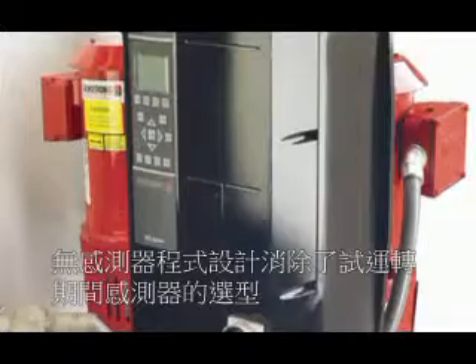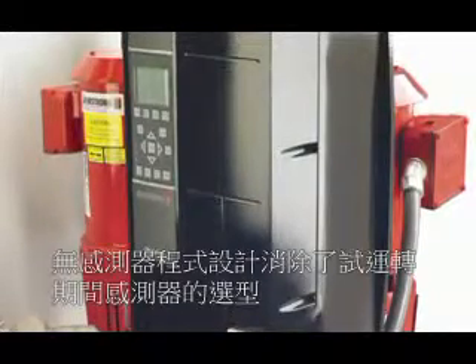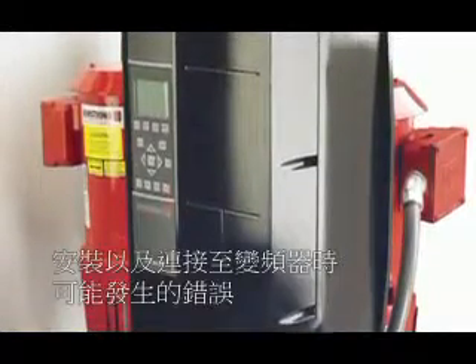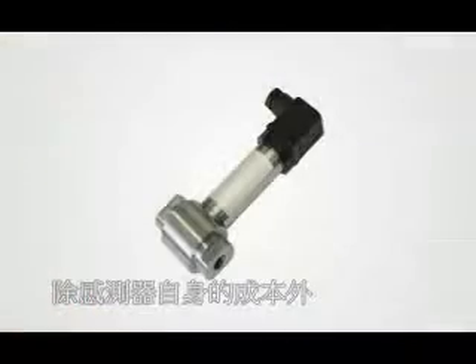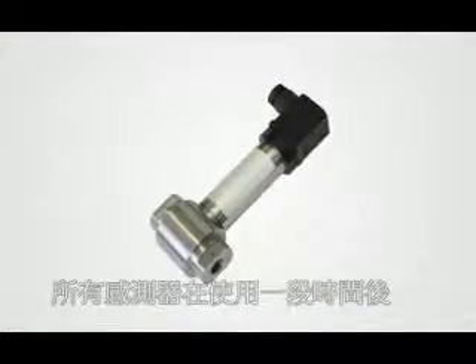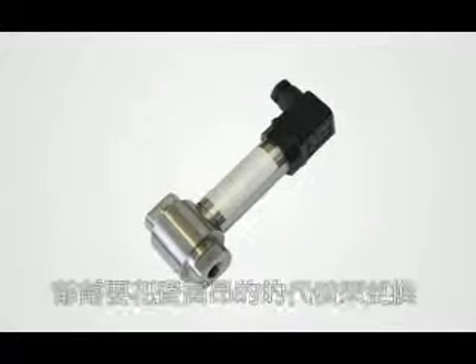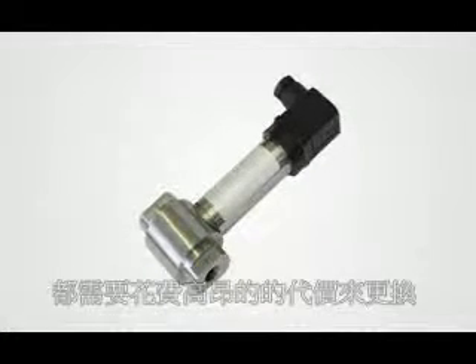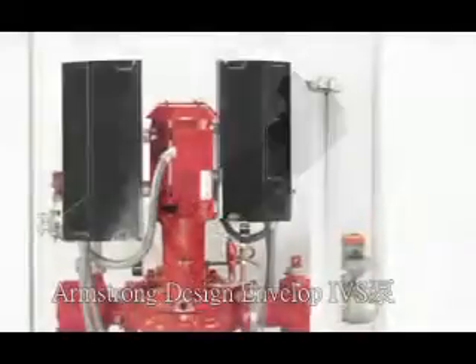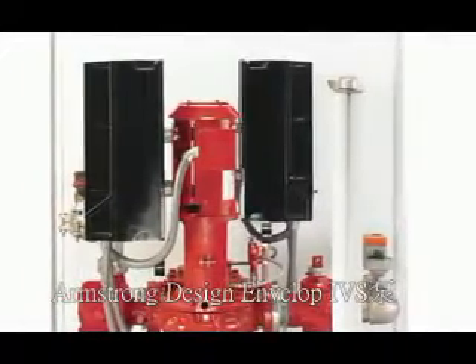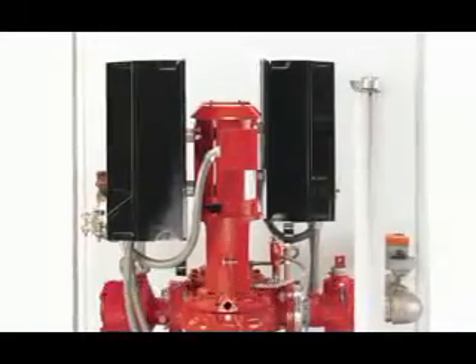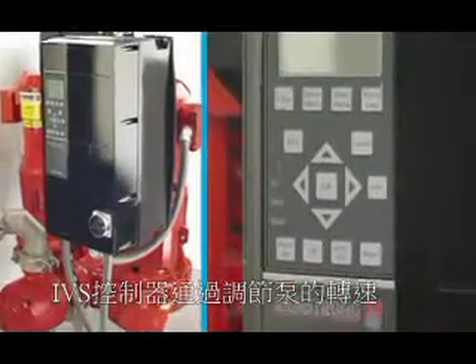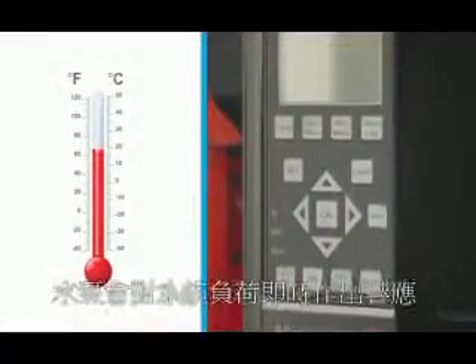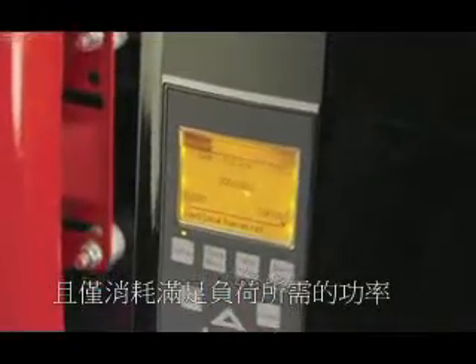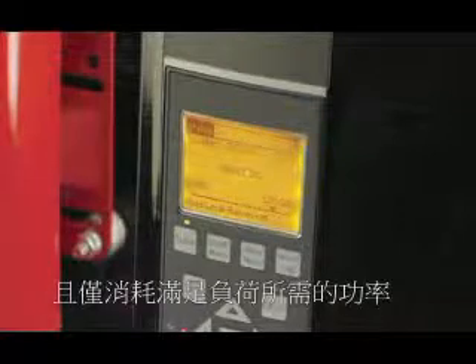Sensorless programming eliminates possible errors in sensor selection, installation, and wiring back to the drives, which can occur during commissioning. All sensors come with the nuisance of costly replacements and repairs that can occur over time, in addition to the capital costs of the sensors themselves. The Armstrong Design Envelope IVS pump eliminates sensors altogether. The IVS controller adjusts the speed of the pump to meet the immediate load of the HVAC system. The pump responds instantly to the system load and draws only the power required to meet the load.